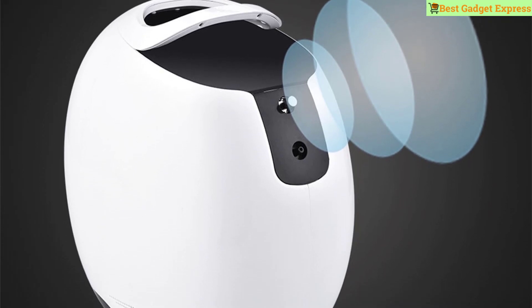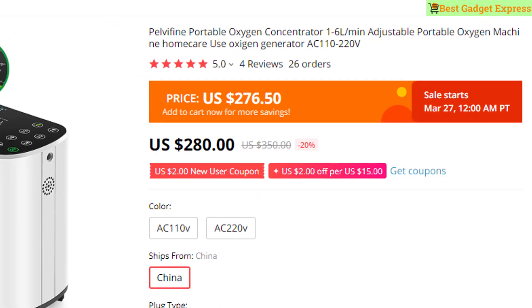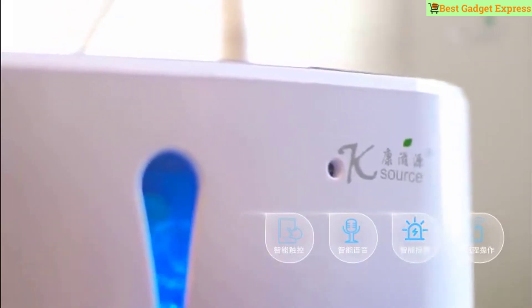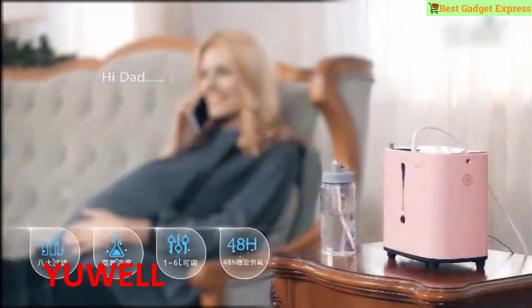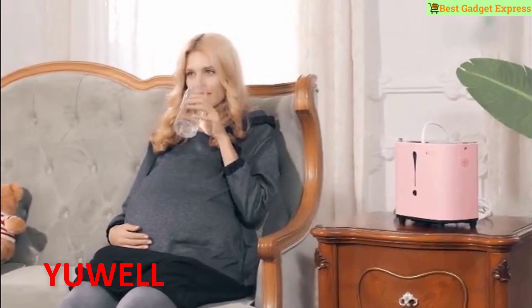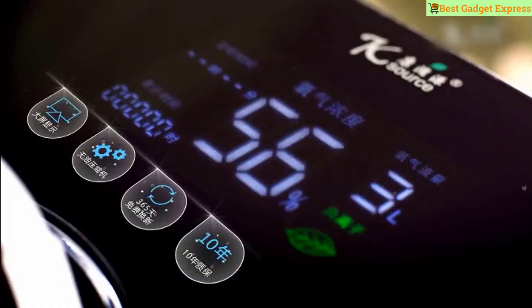Number seven is the Pelvifine Portable Oxygen Concentrator, 1–6 L/min adjustable, home care use, AC 110–220V. Clean alarm every 100 hours — prompt auto-releases after 5 minutes. Filters reusable after cleaning and drying, usually 3–5 times. Filter must be flat during installation to avoid noise. Negative ions about 300,000. Auto power-off for protection.